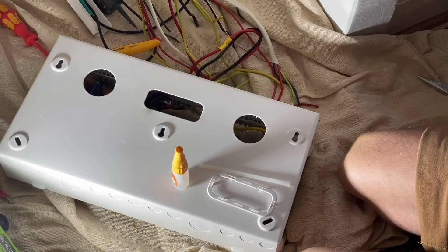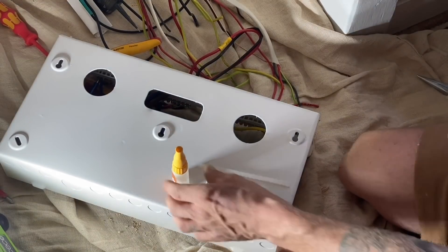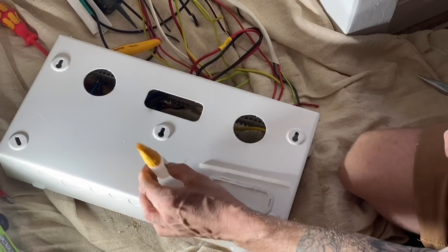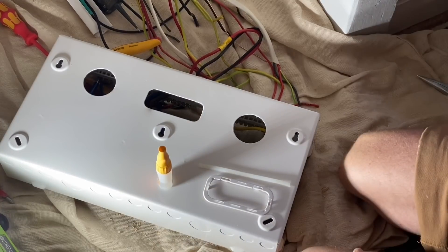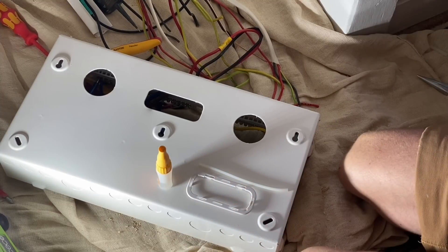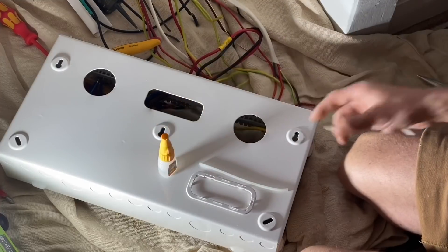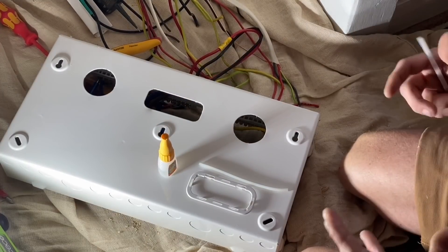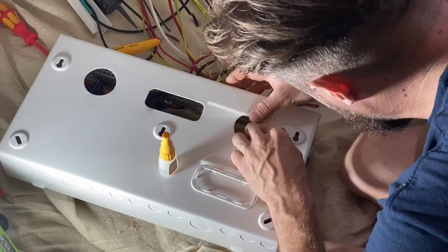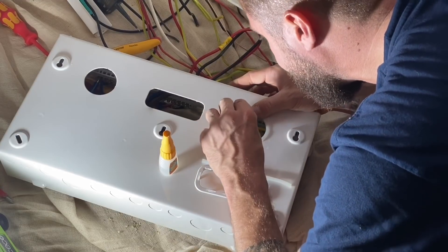You're going to do rear entry on this board, Dan. It comes with all the stuff in the kit — a little plastic bit for the middle which clips in. It shouldn't go anywhere once it's clipped, but I always like to add a bit of super glue just to make sure, because cable entry is very important. I don't think enough people take it seriously — we do need to grommet stuff, we've got sharp metal edges. There's also a grommet strip which I place around the two entry holes — again, a bit of super glue sturdies everything up. Peace of mind knowing the cables are safe. The grommet strip, the other strip, and the blanks were all included in the kit.